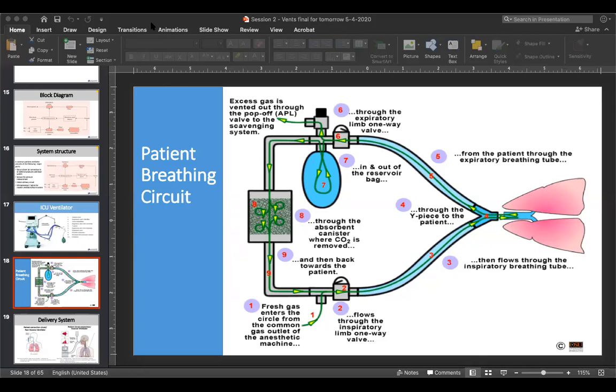So part of the reason is because the anesthesia machine uses a circle loop system. And so it requires constantly watching for moisture in the circuits. It requires constantly watching for the CO2 absorbance, looking at the reservoir bag to make sure that there's no pressure building up in the circuit. There's a lot of other things that come into play besides just turning on a ventilator. And so this is why if you have an anesthesia professional around who can check in on that machine at least once an hour, they can ensure that the device is still performing as the vent parameters that have been set in place.